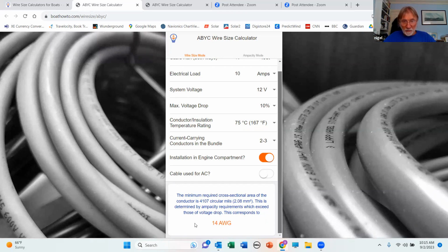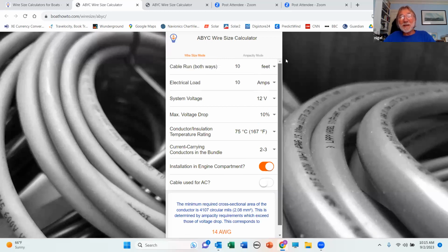And remember, in the US system, when the numbers go, we had what did we have before? I've already forgotten. I'll go back and put the 60 feet in there. I should pay more attention to what I'm doing, shouldn't I? We've got a 12 gauge conductor for voltage drop. So in this case, we've got a larger conductor because we've got that long conductor run, and voltage drop is driving the process. So when we reduce the length of the conductor run down to 10 feet, voltage drop no longer becomes an issue. And we discover that we can actually go to a smaller gauge conductor because of the short conductor run. So there's no great voltage drop issues, and we can get away with a smaller conductor.